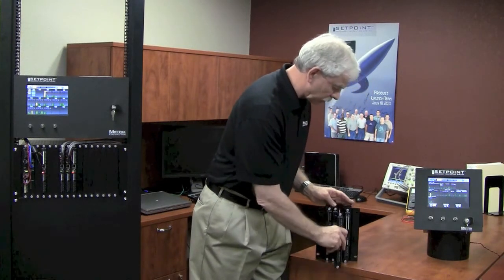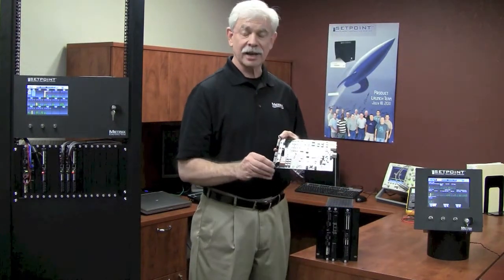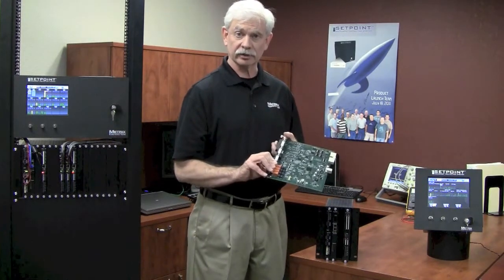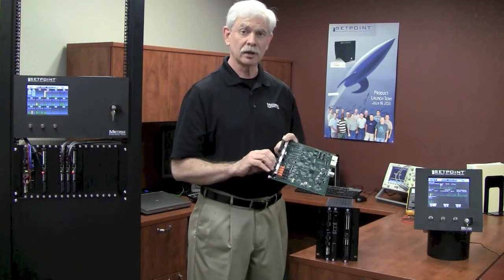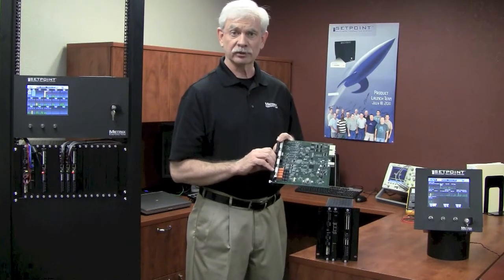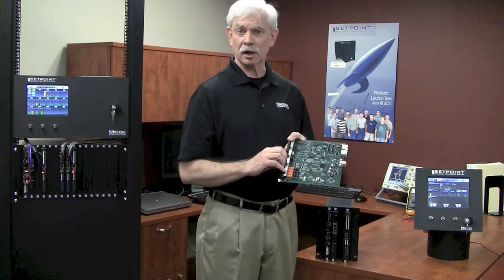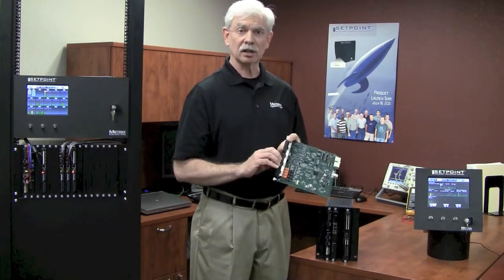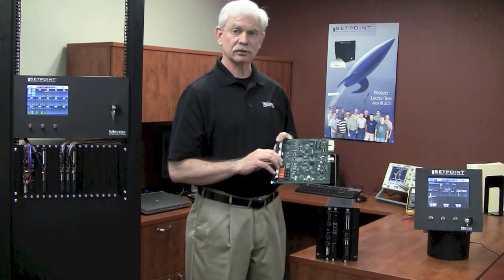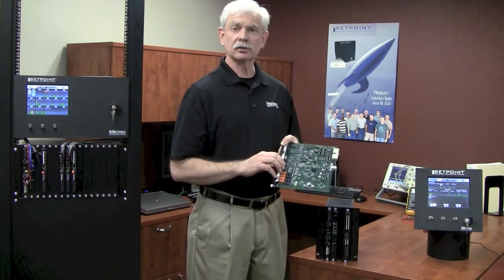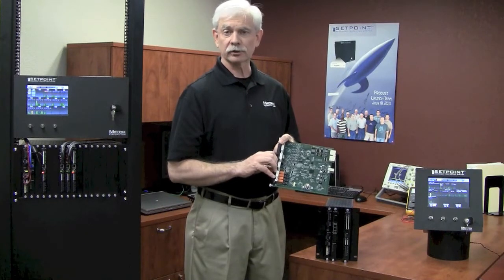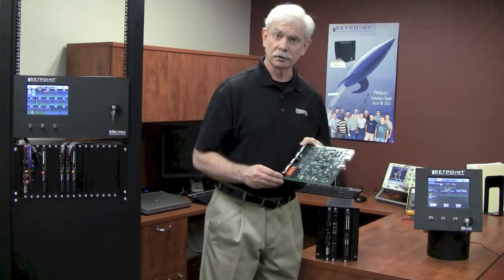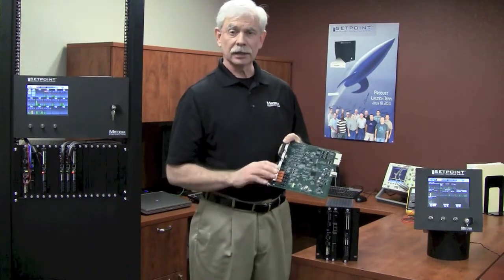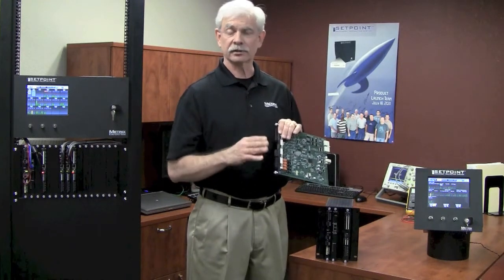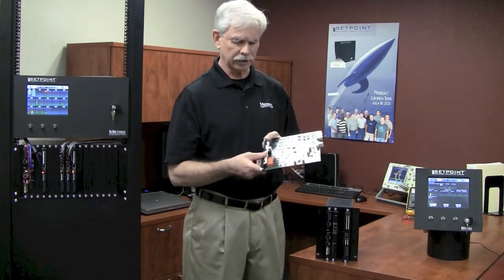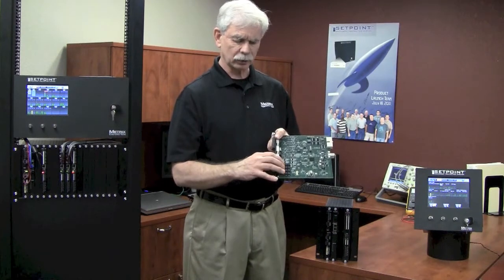It is a four-channel module that can monitor basically everything except temperature in the SETPOINT system. So process variables, vibration probes, velocity probes, accelerometers, case expansion, differential expansion, speed, even discrete inputs. There are close to 30 different measurements that this module can make, so it's very universal and it's designed so that you configure it to make the specific measurements that you want. It's a four-channel device. It has four relays.